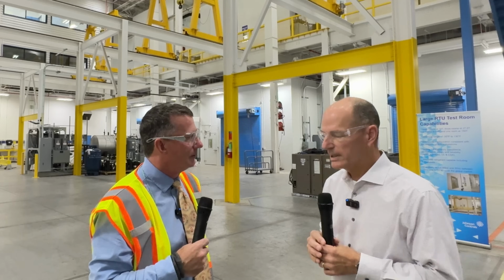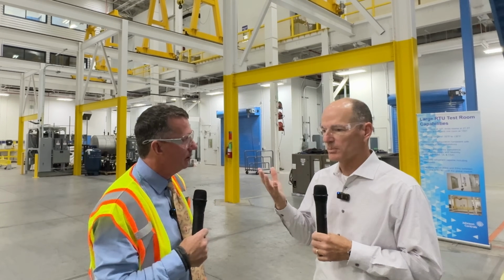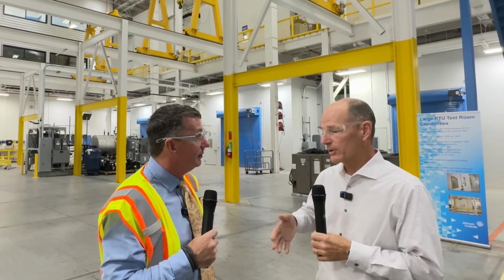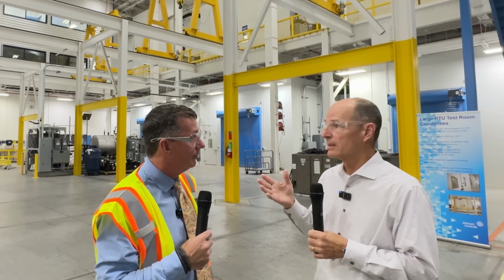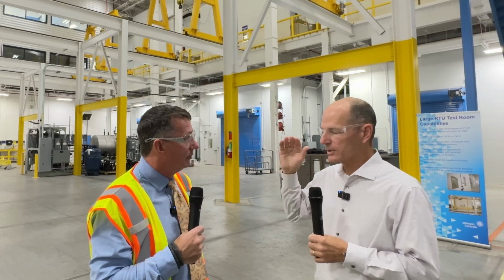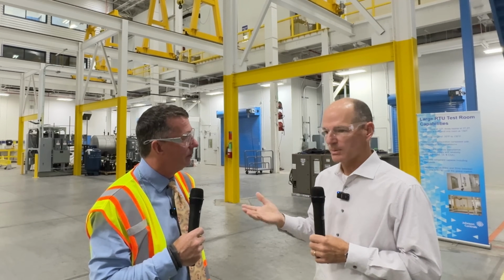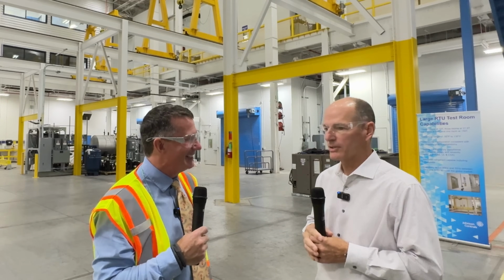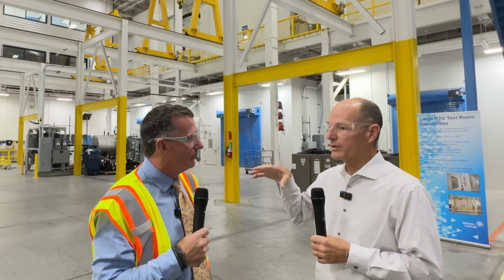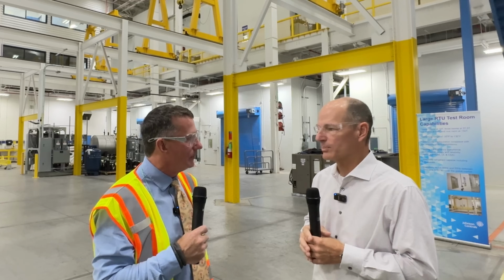These chambers are set up in an over-under configuration, which really simulates how commercial rooftops are installed. Downflow duct orientation, and a lot of capability in the airflow and the temperature range that we can test on the product. So we can simulate the new cold climate heat pump conditions, which is very important. And the over-under arrangement gives us a true representation of how the units apply typically in the field.